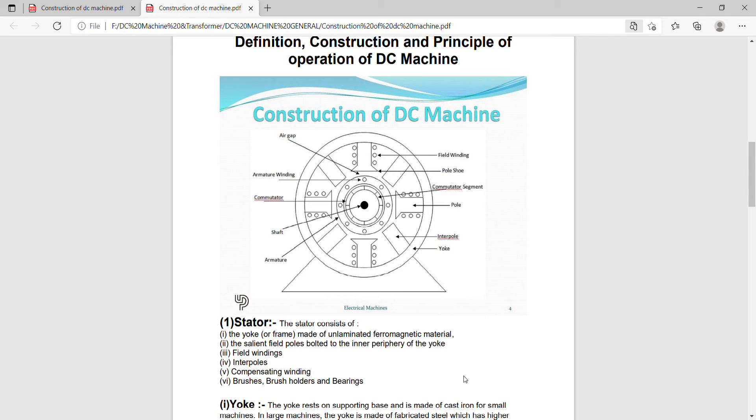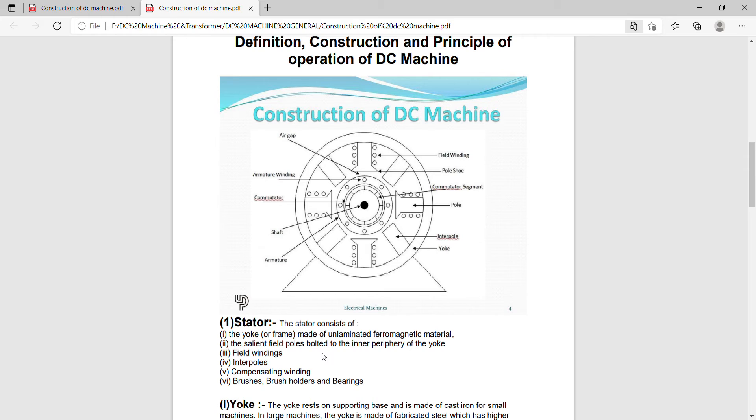The stator consists of the yoke made of un-laminated ferromagnetic material, the salient field poles bolted to the inner periphery of the yoke, field winding, interpoles, compensating winding, brushes, brush holders and bearings. These are the stationary parts of the DC machine.